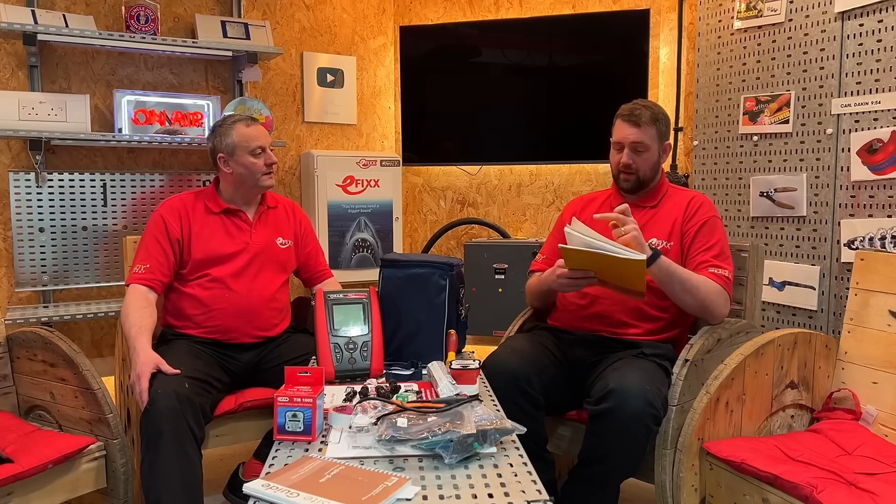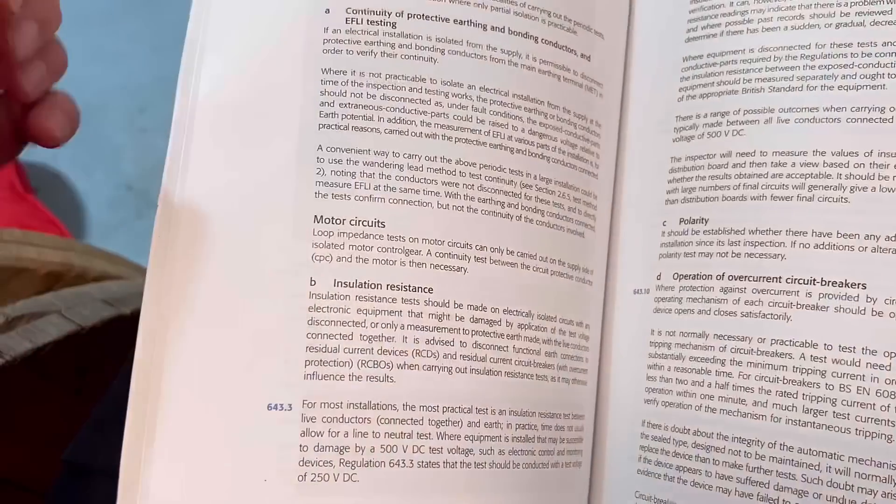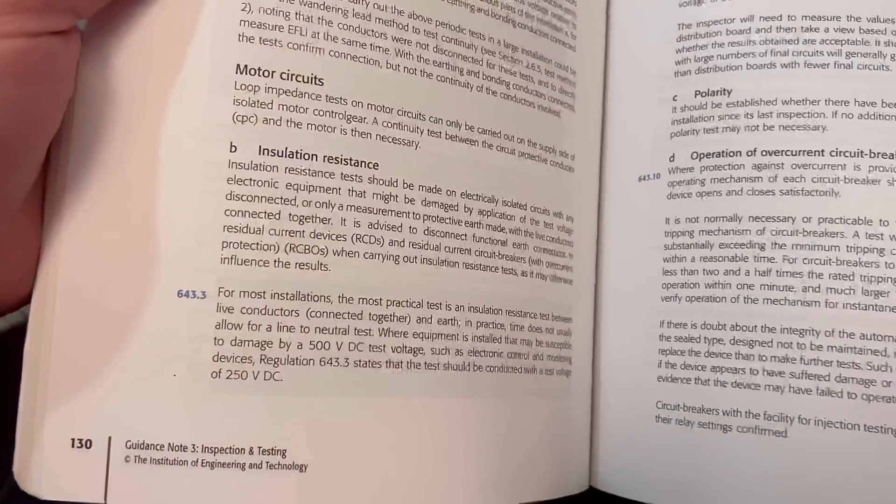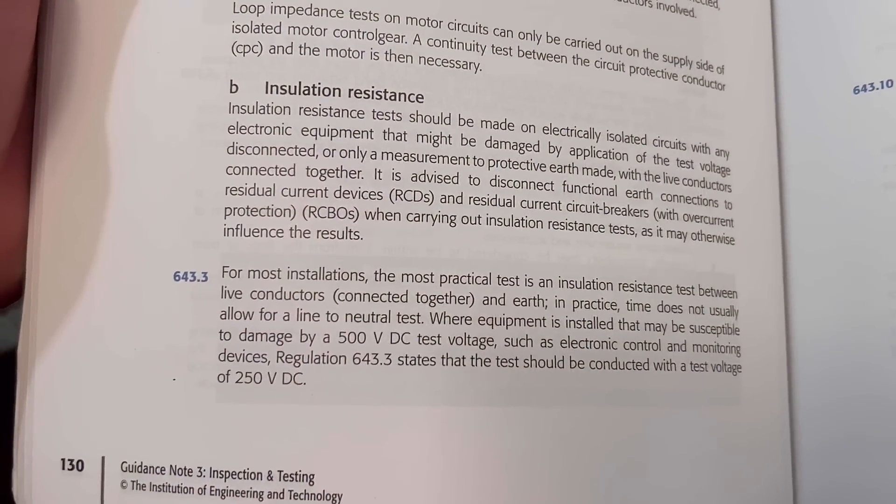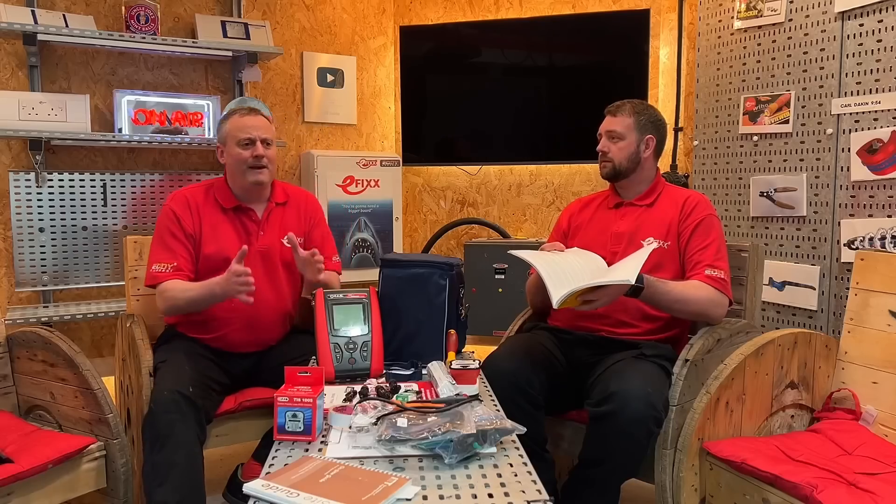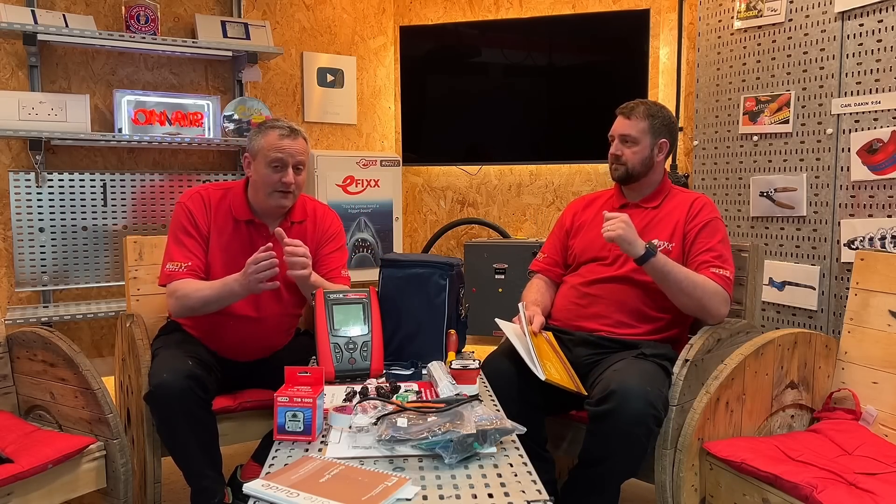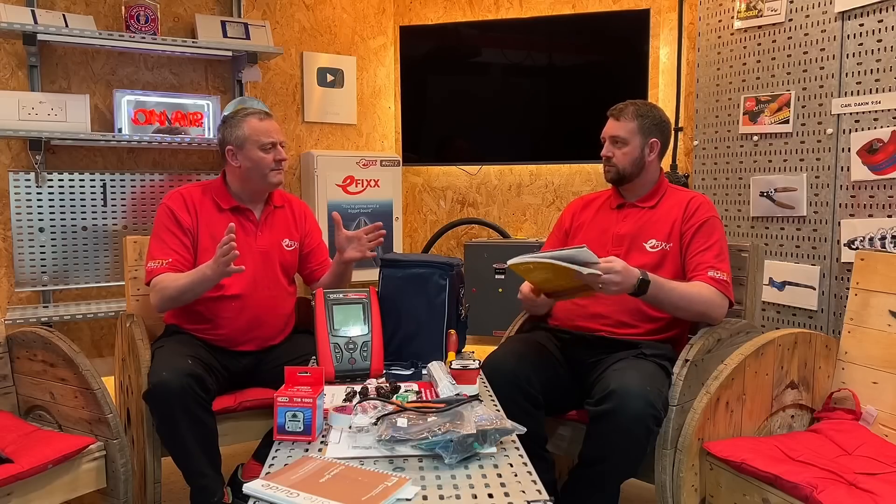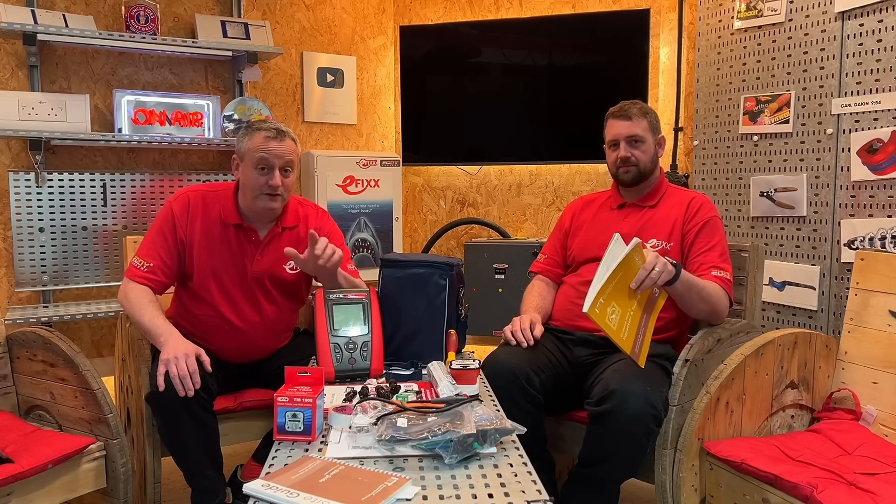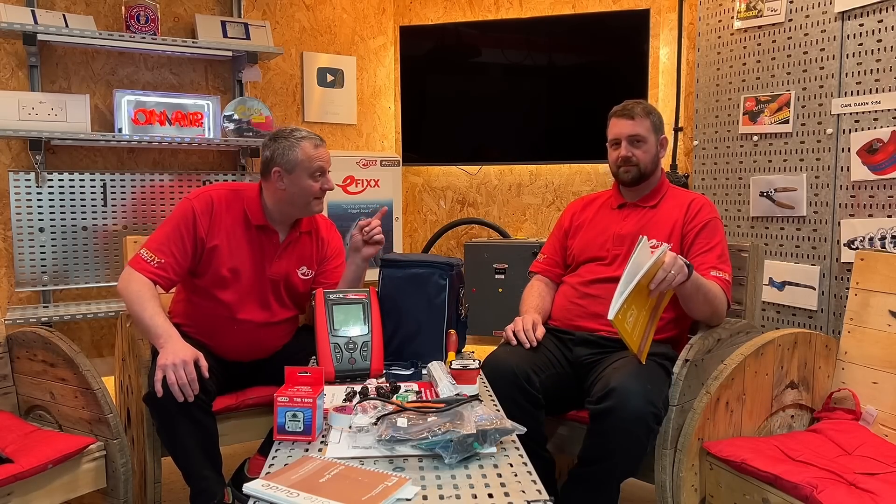However, I've been flicking through Guidance Note 3 and it says here if I link together line and neutral and test to earth, it should be all right. Yeah, but that means we haven't tested between our live conductors. I trust you Rick, but wouldn't it be nice if your multi-function tester's got your back in case you've let me down?